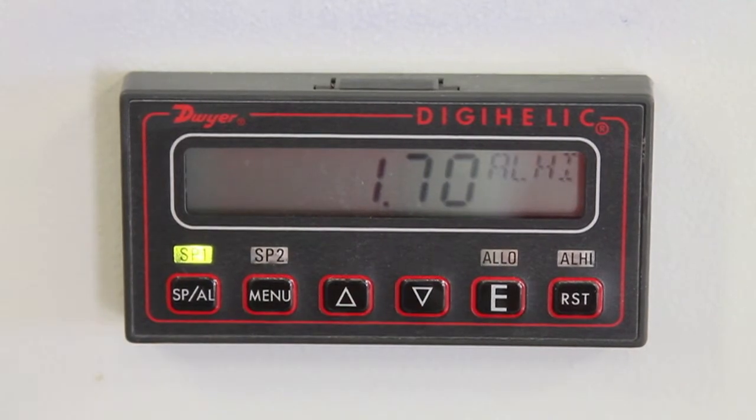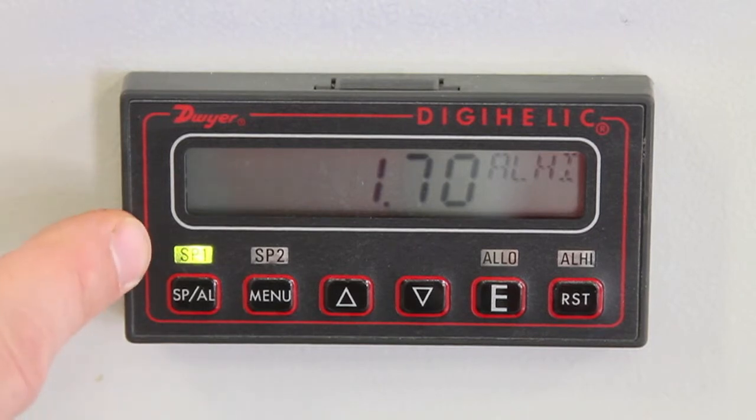We will now start the collector again. The SP1 light is illuminated and it should stay illuminated until we reach our high set point of 1.70. Remember that we do have a 30 second delay before it will call for water. Once it calls for water, it will increase in pressure until it reaches that level and then turn off the fill valve as well as the SP1 light.